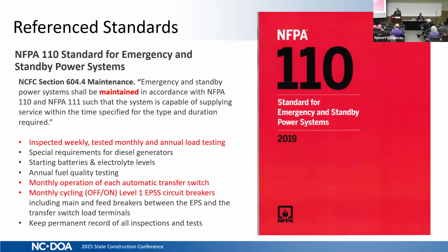But if you see here in the red highlighted items, not only do you need to run and exercise the generator every month, you have to exercise the transfer switch. What that means is when you're running the generator, you need to transfer the transfer switch from normal power to the generator power and back. Because if you don't do that, you're not complying with the direction of the required maintenance. And notice too, the next bullet says that if you have a Level 1 emergency power supply system, which is one supplying life safety, things like emergency lighting, then any breakers between the source generator and the transfer switch need to be cycled on and off as part of that. The point I'm trying to illustrate is that owners need to be aware of these reference standards and be sure that you're following through with all the various tasks in them.